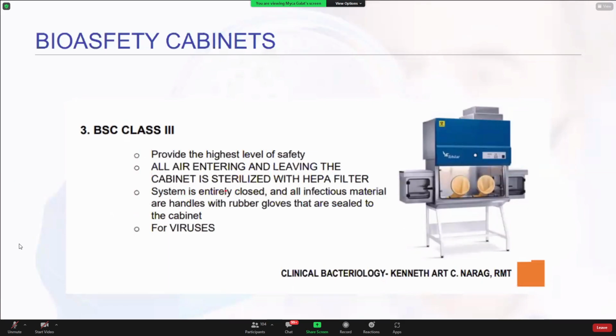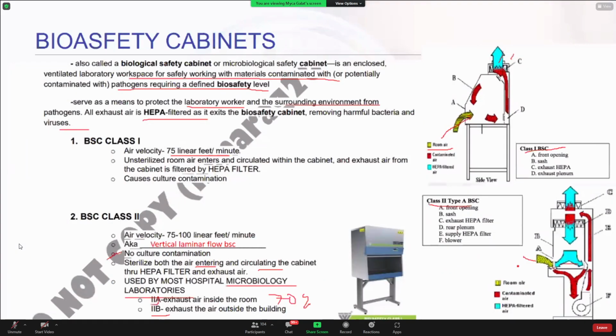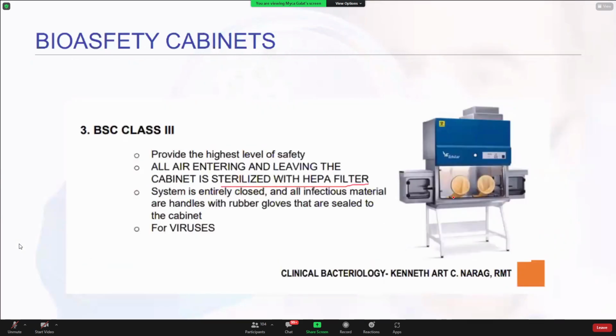So last BSC class, we have BSC class 3. So ito na yung highest level of safety. All air entering and leaving the cabinet is sterilized with HEPA filter. So the system is entirely closed, walang opening. Unlike yung B, di ba sabi ko may opening pa siya, pero yung kasi doon kayo mag-work wala naman siyang lalagyan ng kamay unlike this one. So the system is entirely closed and all infectious materials are handled with rubber gloves that are sealed to the cabinet.